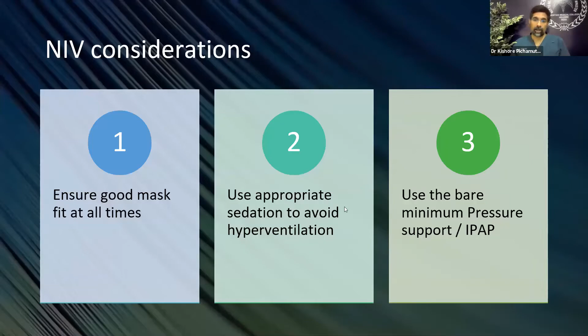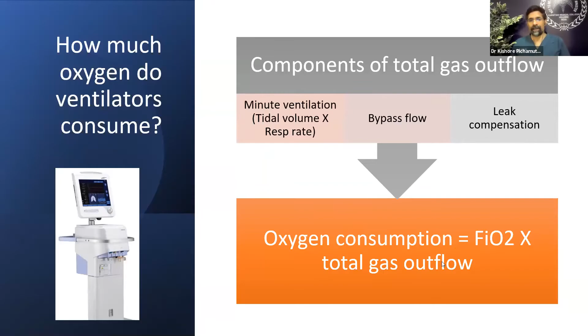Patients on a ventilator: actually, ventilators do not consume that much oxygen when we compare them with some of the other devices. And the oxygen consumption in a ventilator, most of it, you can see right on the screen when you're standing in front of the ventilator: it's the minute ventilation. The minute ventilation times the FiO2 will give you the total oxygen outflow. Therefore, if you're able to minimize the minute ventilation and minimize the FiO2, you're going to reduce the oxygen consumption.